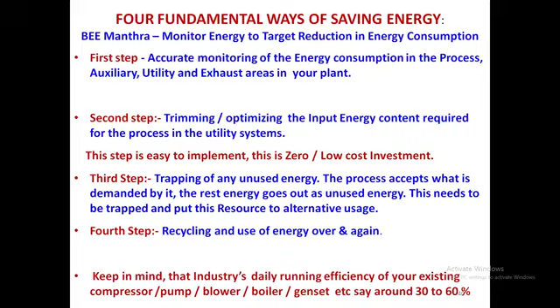The third step is, whatever the equipment is getting, let us say the compressor is running, a lot of heat is wasted through the exhaust. How can this be recovered, how can this be put to use? When I worked in a Dutch user group, they said, from Holland, we are not allowed to waste water of more than 40 degrees centigrade as effluent from the industry. Whereas in our place, more than 60 to 70 degrees hot water is getting wasted as effluent. So for trapping or recovering the heat embedded in the system, ultimately the m Cp delta T plays a major role, and the heat embedded in the water that is getting wasted needs to be retrieved. This is where we are concentrating more now, and recycling wherever possible, over and over again.